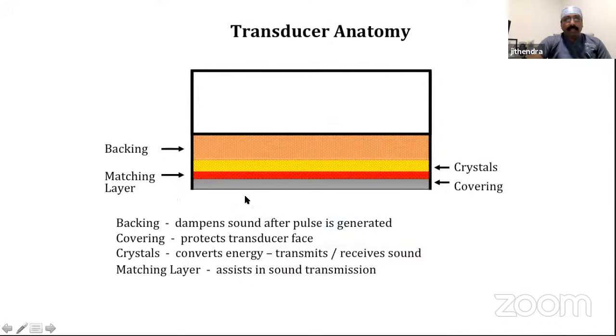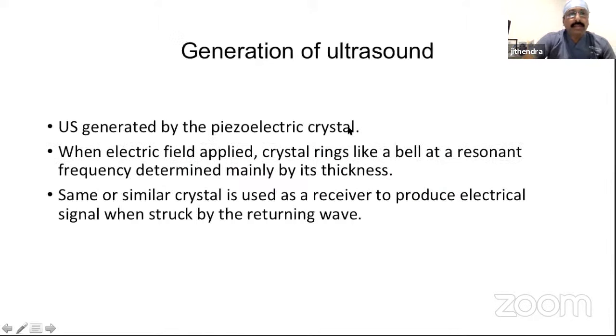Now the same thing is the transducer anatomy. What you see, there's a backing material, and this is the covering of the probe, the footprint of the probe, and you have the crystals arranged over here just beneath the backing material, and between the backing material and the layer, there's a matching material which augments the sound waves.